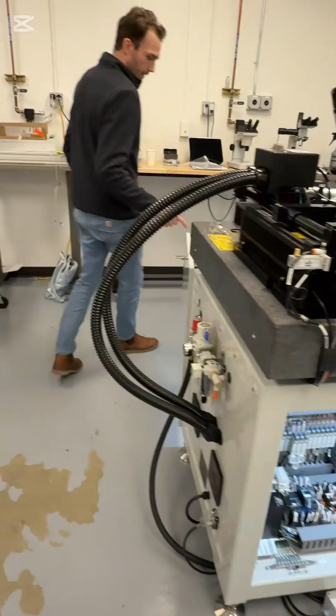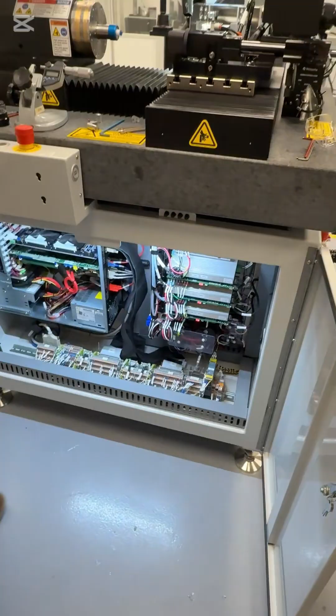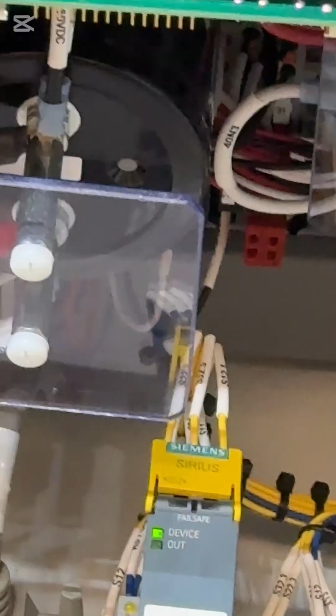Now, one more area right here. This is called the safety relay. It's just a safety measure. It pretty much protects you from turning on the amplifiers when there's some sort of fault in the electrical system. So you want to have 24 volts, and the way you know you have 24 volts going to the safety relay system is if this device LED is on. If the green light is on, it means this relay is working. Now you'll notice when I release the stop and press amp power on, it's going to initialize here. You'll notice that the output light is now on.